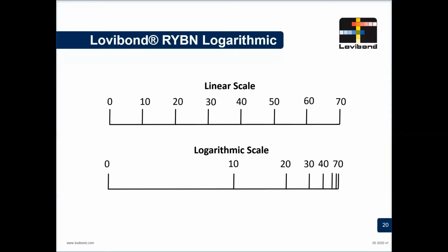We also need to remember, if we're looking at the Lovibond scale or the AOCS Tintometer scale, that they're not linear scales, they are logarithmic scales. So as you get darker, the colors get closer and closer together. If you have a color around the 5, 10 level, you can have quite a range for a small number range. If I'm higher up the scale, maybe 40 or 50, everything's very close together. So is my number 40, 50, 60? Not much difference in the color.